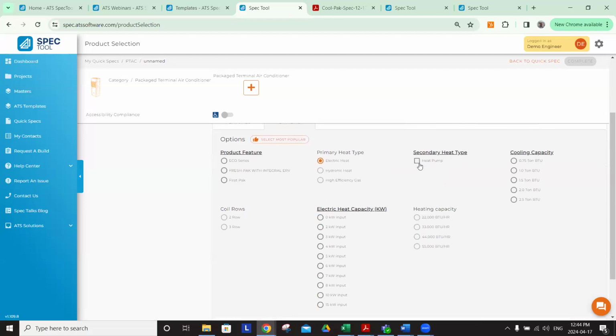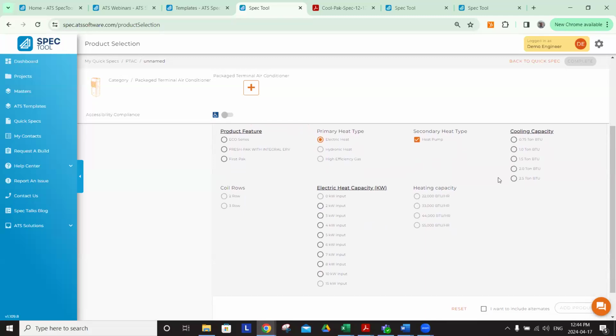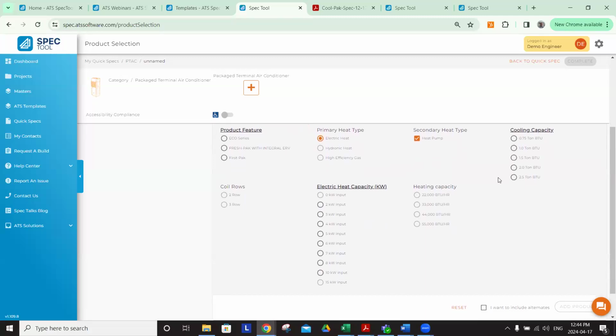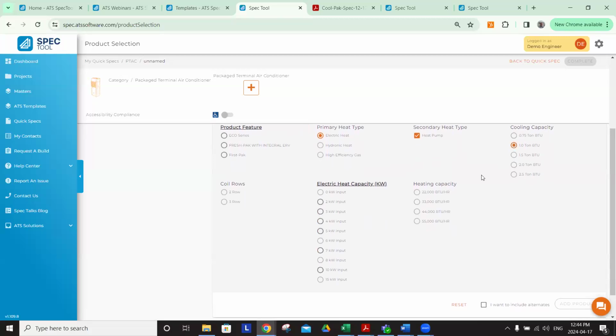And now we want to include our heat pump as a secondary heat option, right? Yep, let's do that. You don't have to. There is an electric heat only version, but heat pumps are certainly going to bring your energy usage costs down. Perfect. And then you can choose the size that you'd like. Let's say 1 ton. Yep, so 12,000 BTUs. Very common in these spaces.